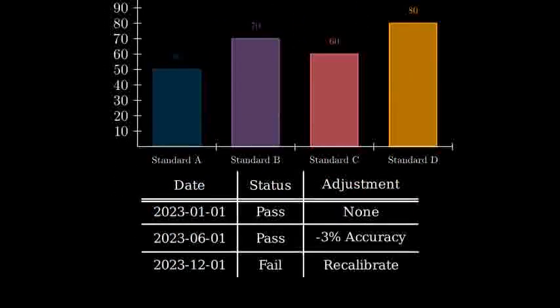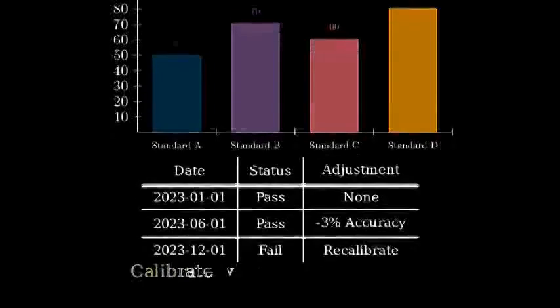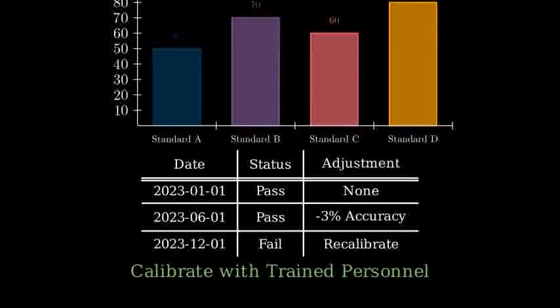Always make sure to adhere to industry-specific standards and regulations regarding calibration frequency for gas detectors. Calibration history can give insights into past performances and may indicate the need for adjustment in calibration frequency. Calibration should always be conducted by trained personnel using proper calibration gas and equipment. Following these guidelines ensures accurate and reliable operation of your Crowcon gas detector.